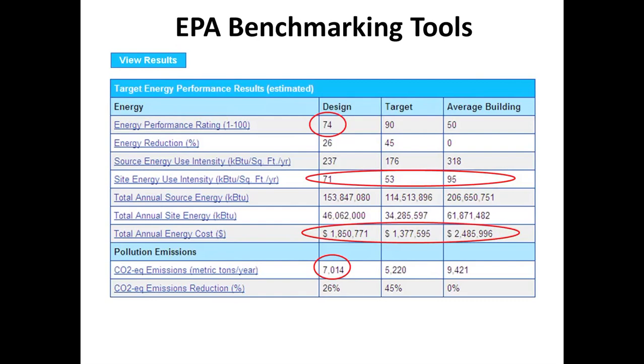That gives us that site energy use intensity number, which is really going to be a driver of these softwares. It's going to be the total amount of energy used at the site on a per square foot basis per year. Our target says that right now we're at 71, and in order to have a building with a score of 90, we need to reduce energy consumption to a total site energy use intensity number of 53. So this can help define goals and allow us to see what we would need to do in order to achieve a higher rating than we already have.